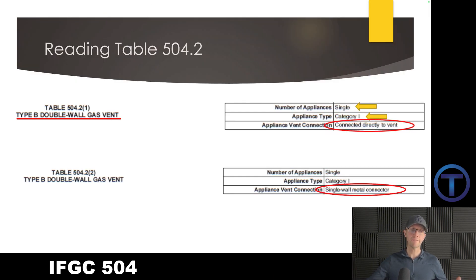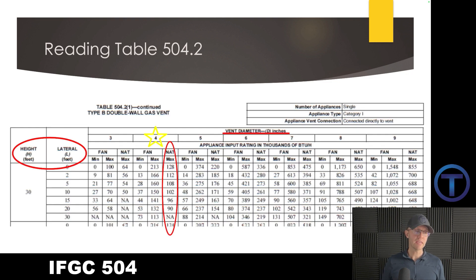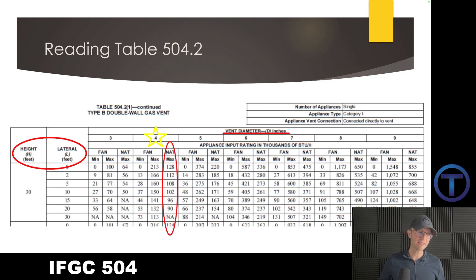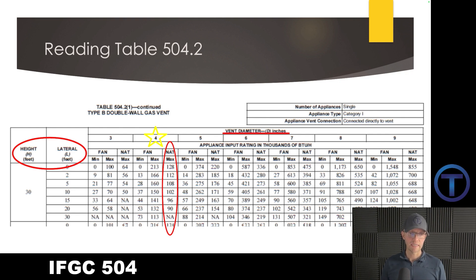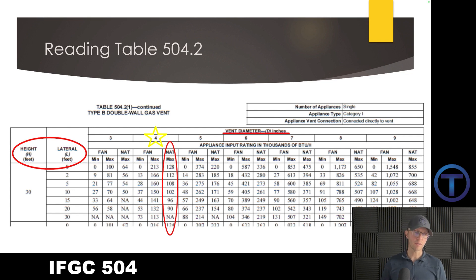Let's focus on what we deal with. We would be doing a type B double wall gas vent, and we can install that connected directly to the appliance or hooking up a single wall connector. Then we can start using these tables. Once we've figured out which table to use, we get right down into the nitty gritty of the table itself to find out the size of the vent. Not only do we need to know the vent type, like B vent, single, Category 1 — but we also need to know the height.